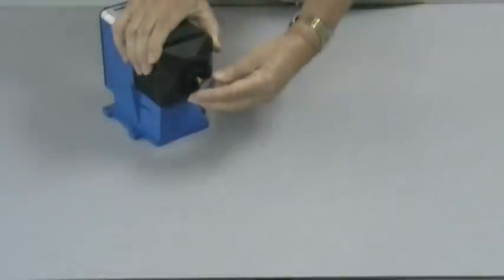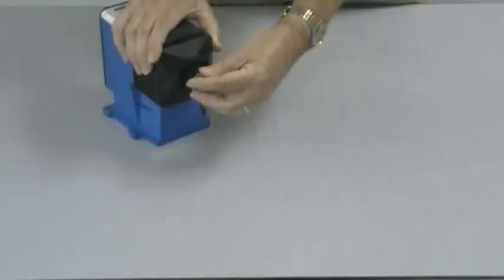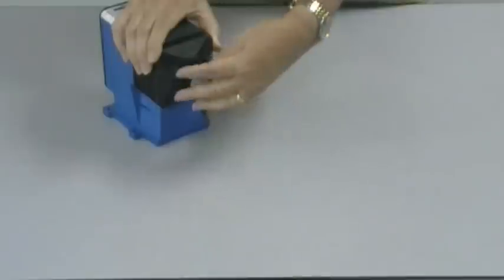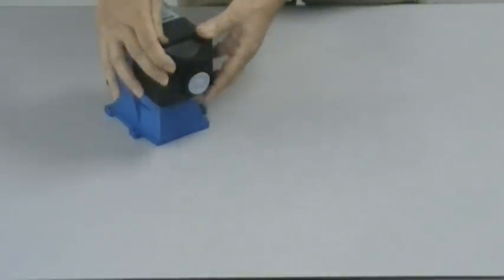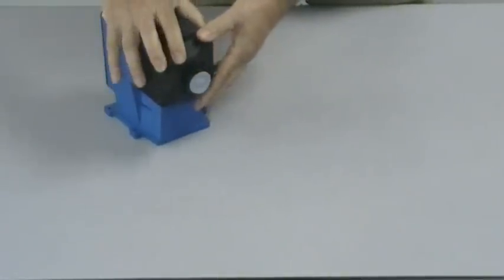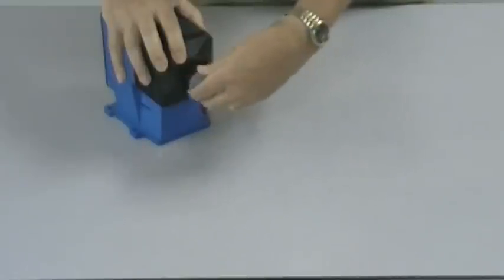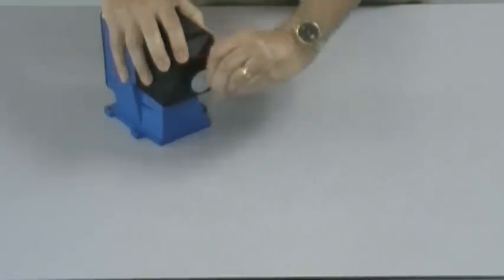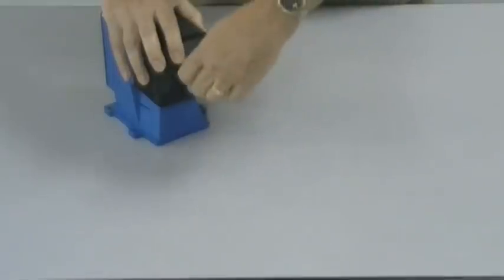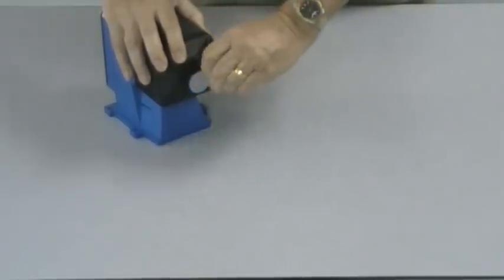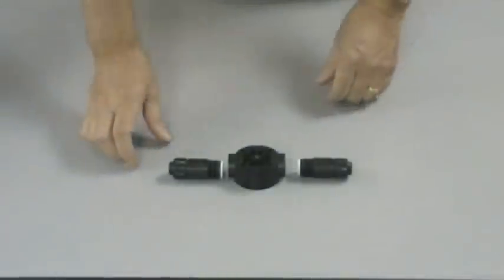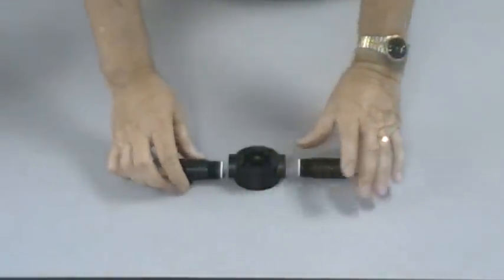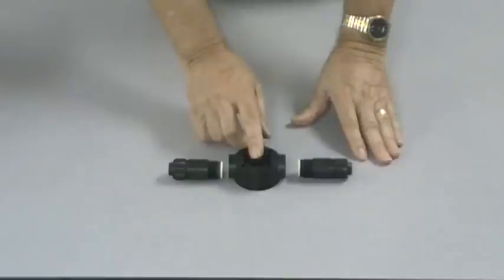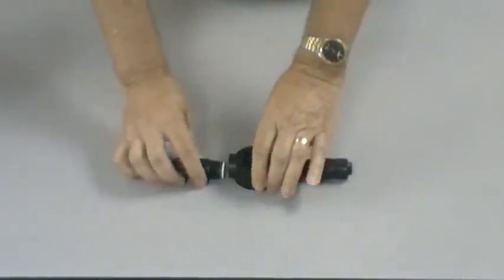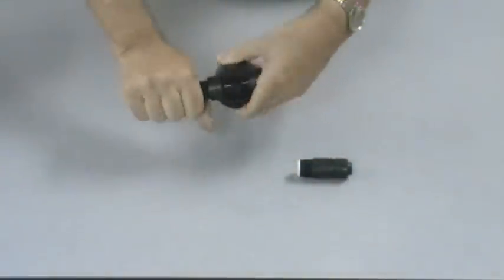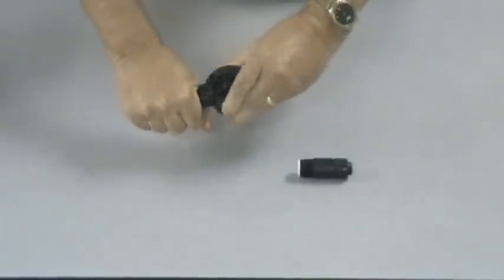Then the diaphragm assembly is threaded onto the end of the shaft, assuring that the adapter plate is in position all the way back. Turn the diaphragm until it stops. Now we will assemble the pump head assembly: the suction valve, the pump head, and the discharge valve. All three of these parts have arrows on them that indicate the direction of flow.